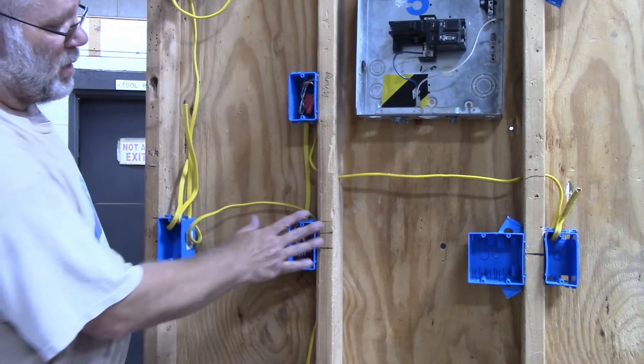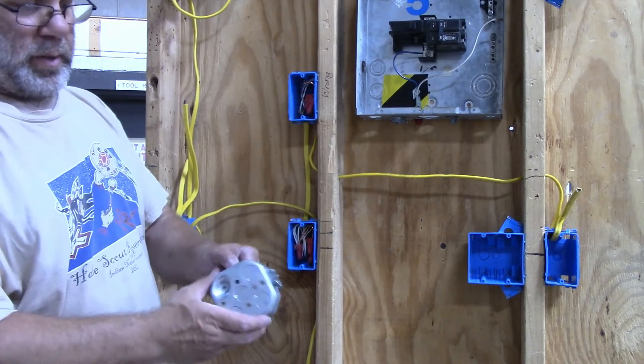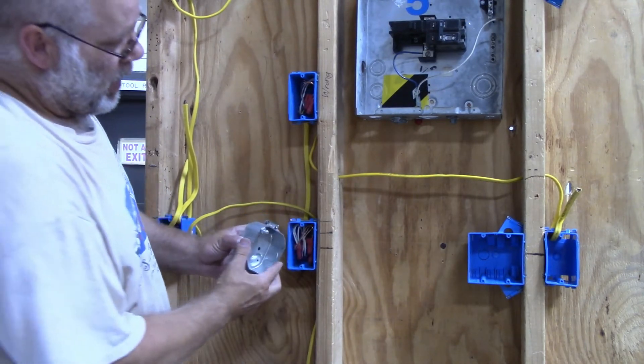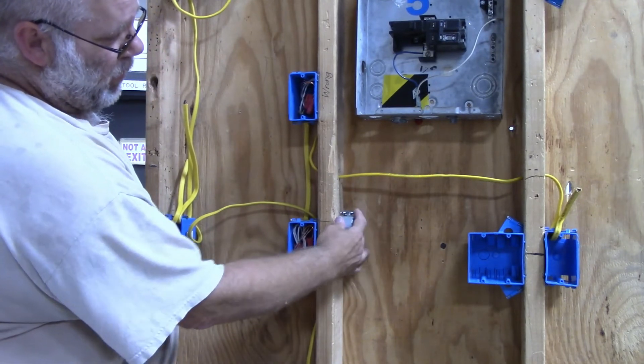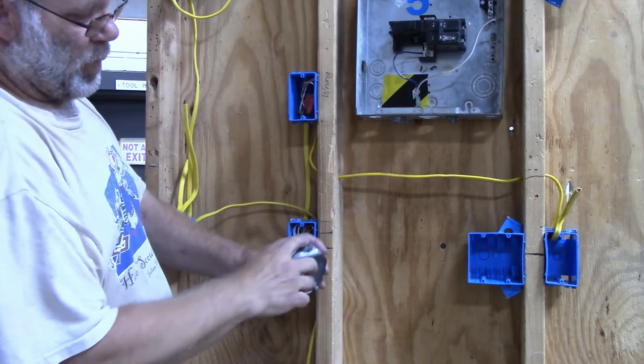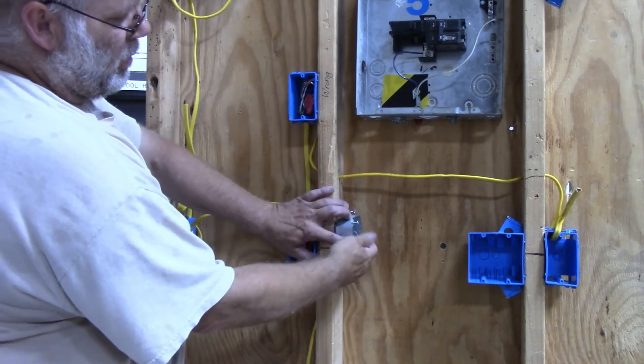So you can use these single gang boxes like this. You can use this octagon box, and you can mount it on the inside of the stud like this, and put a blank cover on it when you get done. Romex connector, run the Romex into the Romex connector, and do all your work here.